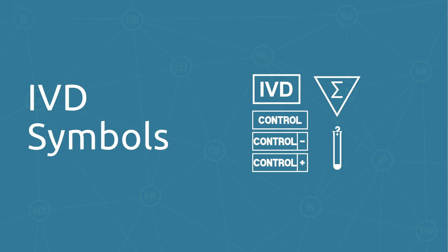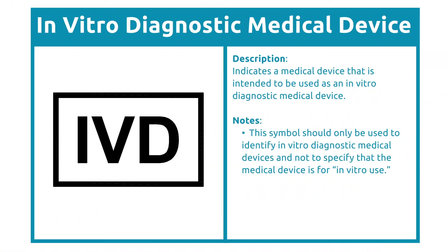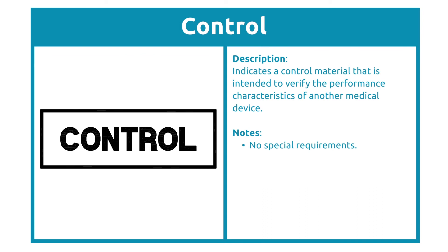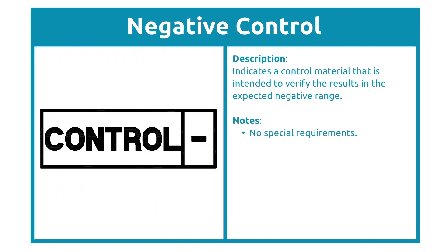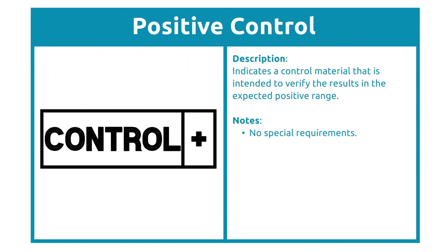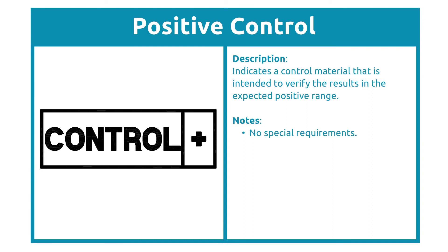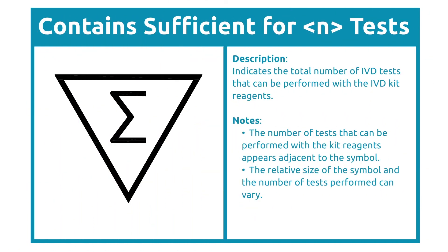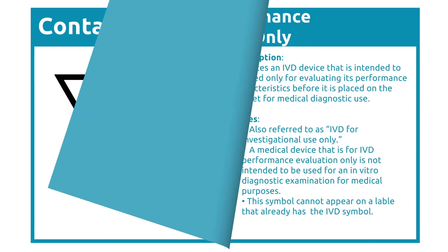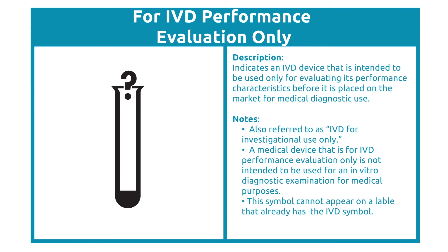IVD symbols are specifically used on in vitro diagnostic devices and communicate information germane to those product types. The IVD symbol identifies in vitro diagnostic devices — there is an important distinction between IVDs and medical devices. The Control symbol identifies devices used to verify the performance of another medical device. The negative control symbol identifies control material intended to verify results in the expected negative range, while the positive control symbol identifies material intended to verify results in the expected positive range. Another symbol indicates the maximum number of tests that can be performed with the IVD kit. A separate symbol is seen on IVD devices used for investigational purposes and cannot appear on a label that also has the IVD symbol, as it is not intended for medical use.